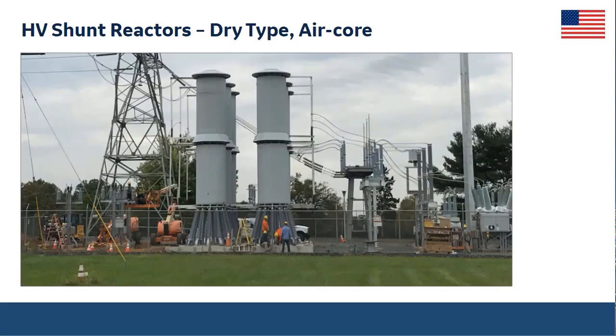Now, you should ask me, okay, so air core dry type makes a lot of sense to use, right? It's most probably cost effective, lower price, no maintenance, simple design, no failure. So why do we still have the traditional oil-filled iron core design? To be honest with you, the reason is the footprint. The air core dry type may require more space than the traditional oil-filled unit, mainly because of the magnetic field of the equipment.